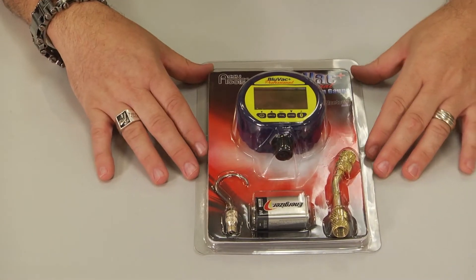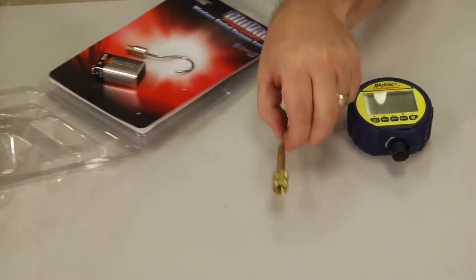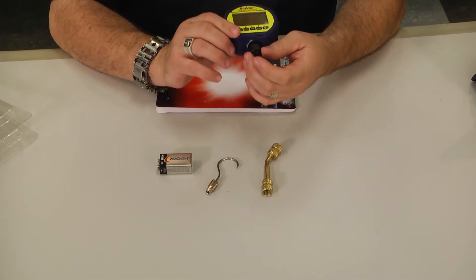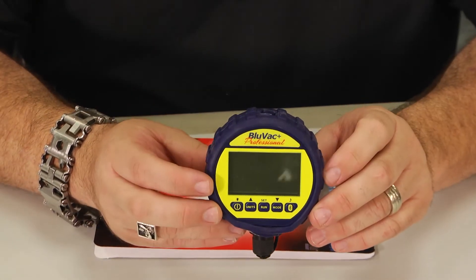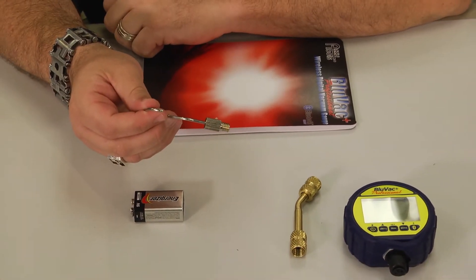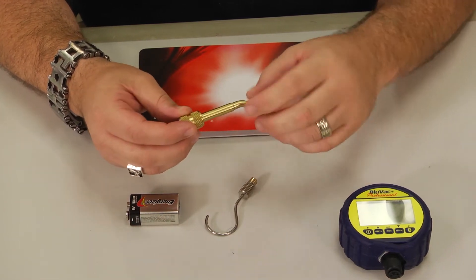Let's go ahead and unbox the BluVac Micron Gauge to show you what you get. In the box, you're going to get the BluVac Micron Gauge itself, with a threaded fitting, and it comes in a rubberized jacket to protect it from shocks and drops — because drops and shocks are usually what sends things out of calibration, even digital equipment. You also get a fitting that threads onto the top so you can hang it while checking the system, an offset adapter that gives you a 45-degree angle for easy hookup, and the battery.